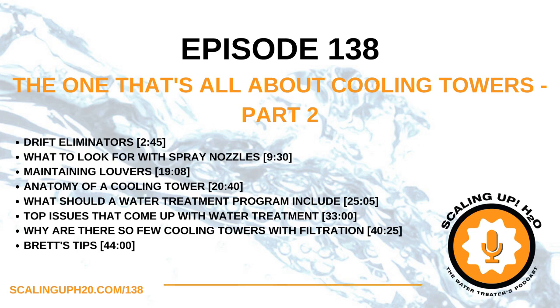Brett, let me ask you, I've seen systems where people have tapped off the riser pipe and then drilled back into the side body of the cooling tower to allow the water to return to the basin. How do you guys feel about that? That's a difficult thing because we sell water treatment equipment that is factory mounted on our units. So I kind of have a point. This is one where I'm conflicted, where I try not to give too many recommendations on where you should drill holes in our units. The one thing I will say is that when you're returning it to the basin, through the louver or through the PVC, that might be the best spot. That supply line should make sure it goes below the coil.